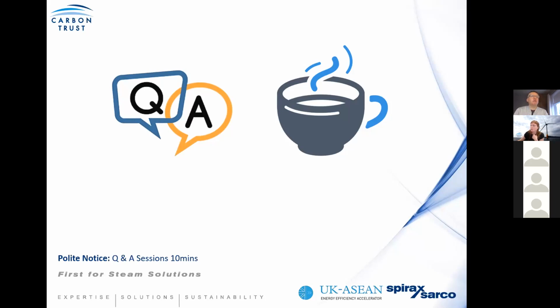Again, it's important to remove the wet steam before it gets to the distribution system. If your steam system has an external distribution system, you should do so on entry into the building, because where you have an external distribution system, your steam header is open to the environment. From the geography, the rainy seasons in Asia, a lot of rain, wind, etc., can have an impact on the heat loss in the external distribution system. So it's important to put it where the header enters the building. Finally, for critical end process users, where it's important to have good control of, say, a certain heating application, you should also install it there. So 3 key locations. Okay.